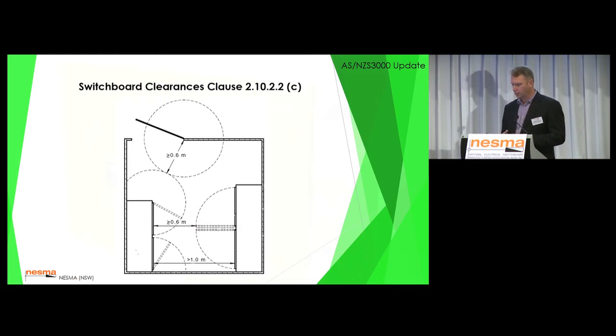Here's another example where we've got two switchboards facing each other, and this was one of the issues that we always had. Some inspectors would issue defects where we had two doors open at the same time and they required 600 clearance between them. That's no longer the case. The likelihood of working on both switchboards at the same time is quite low, and they've accepted that you can do this 600 clearance with only one of the doors open, but you should choose the widest door.